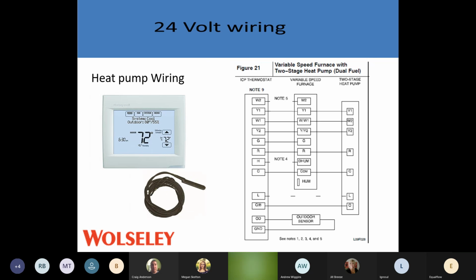Heat pump application. The heat pump is now an air conditioner. So there's other things that you need to look at. You need to look at your O terminal. Your O terminal is going to be energized, which is your reversing valve. You're going to need to make sure that you have 24 volts on O. You're going to need 24 volts on your R, Y1, Y2 as well. So these are things that you need to look at, especially when you're on a heat pump. A little bit more going on there. We need to energize that reversing valve as well.